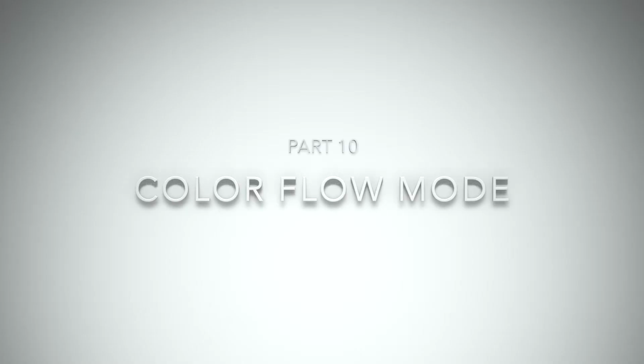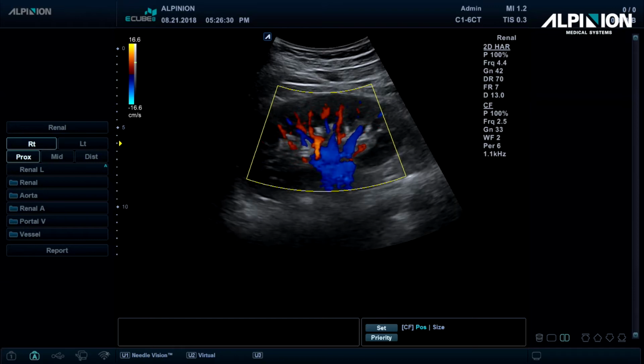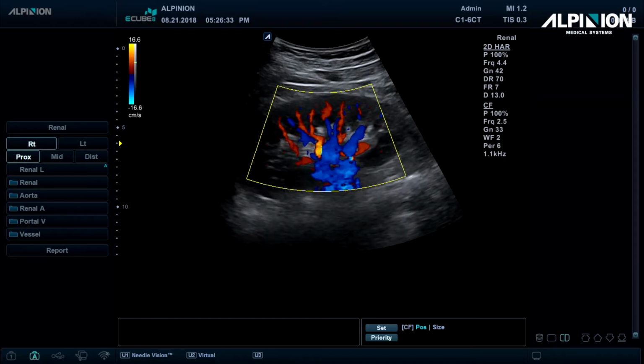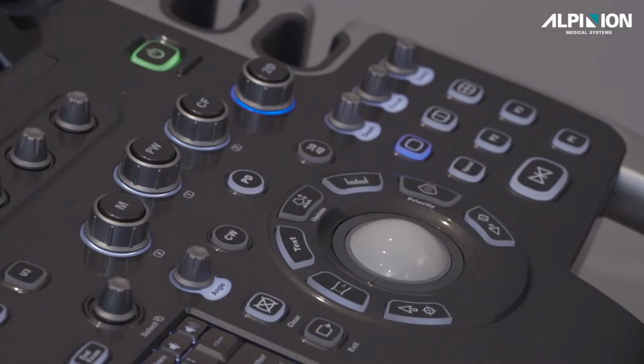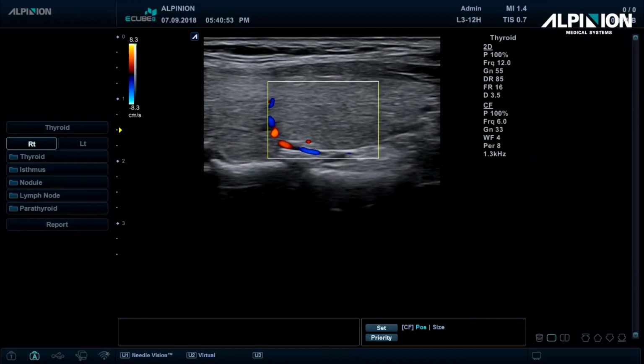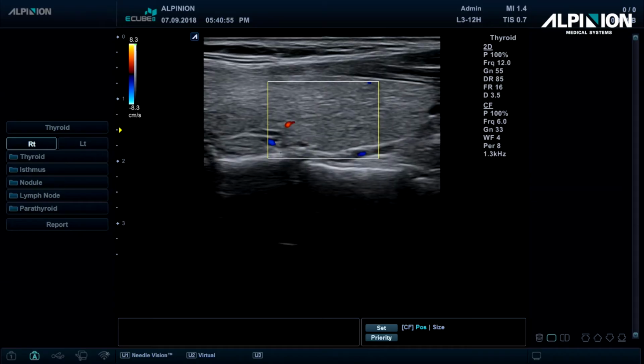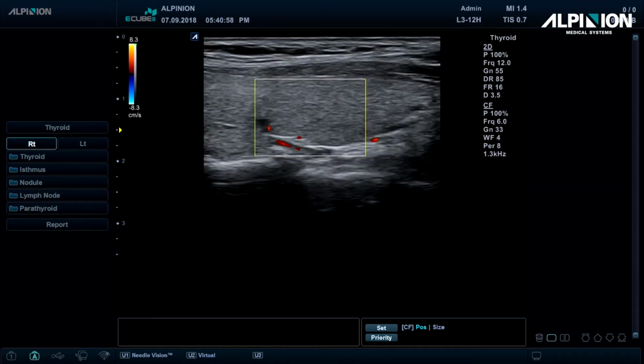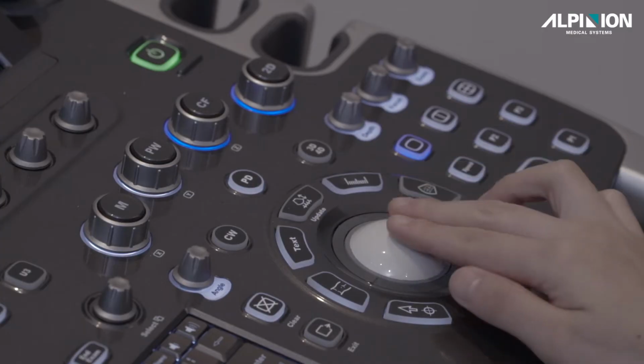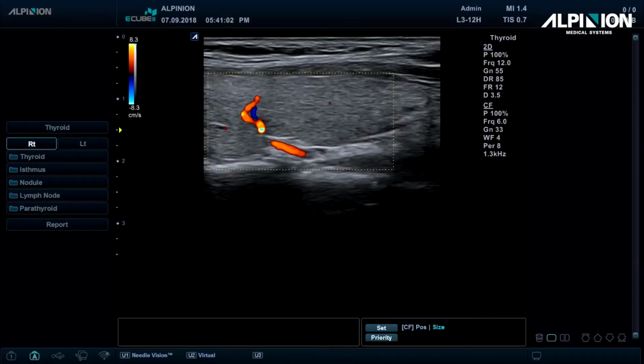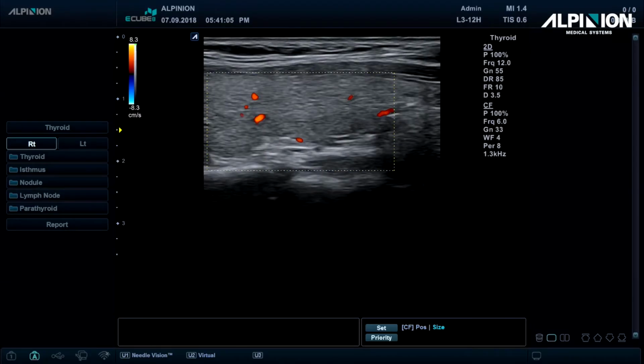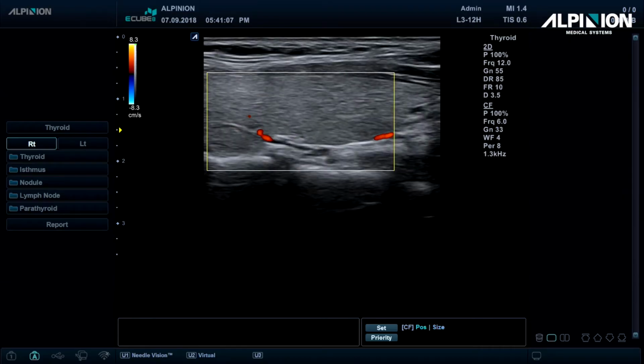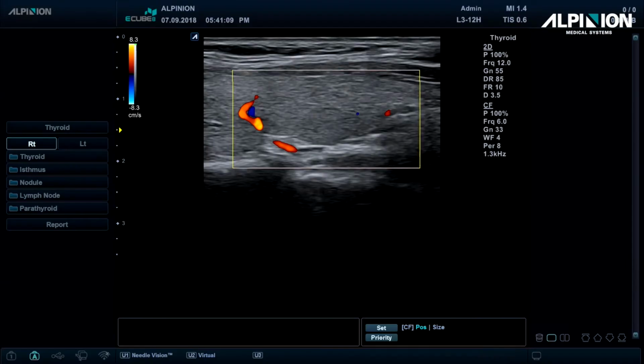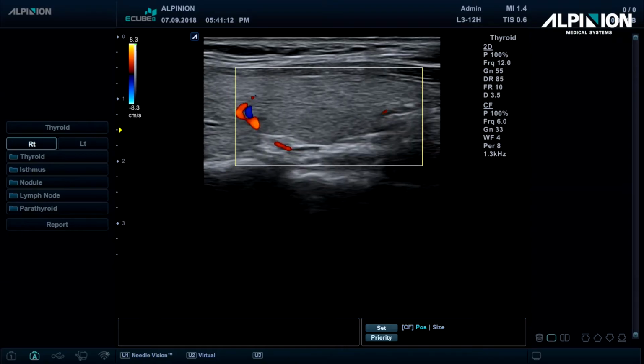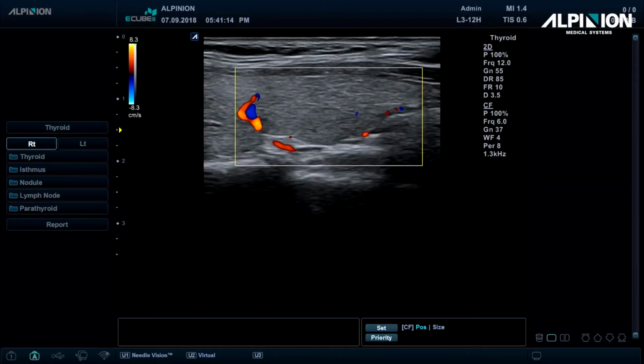Part 10. Color Flow Mode. Color Flow Mode is the imaging mode that depicts the velocity and direction of blood flow in a color map. Once you press your Color Flow button, you can see the color box appear. To adjust the size of the color box, press the Set key and modify the size of it, and press the Set key again to fix this size. By using your trackball, you can locate your box on the region of interest. A very wide box can cause a lower frame rate.